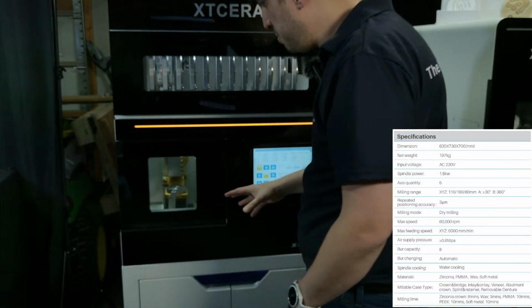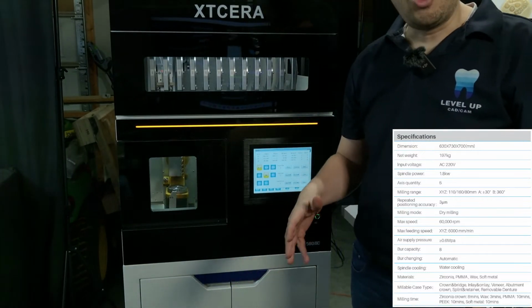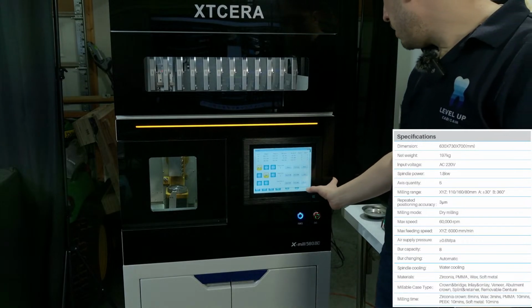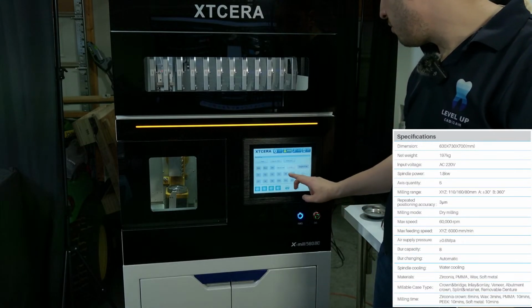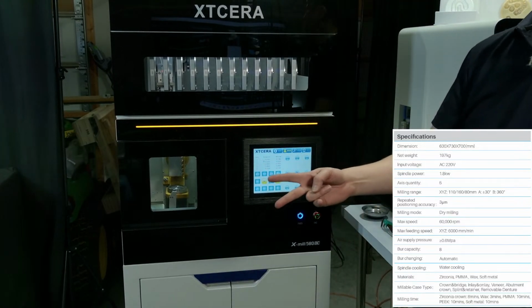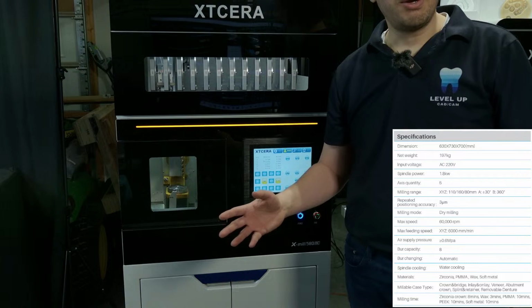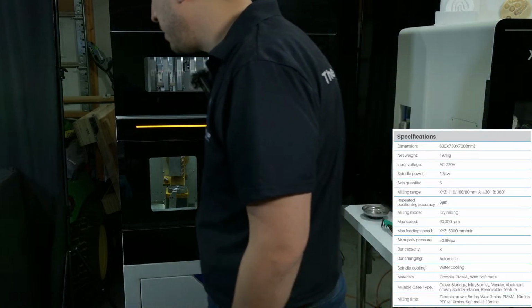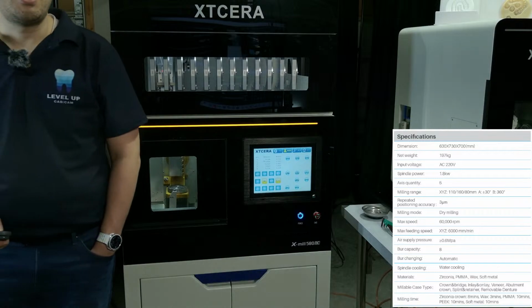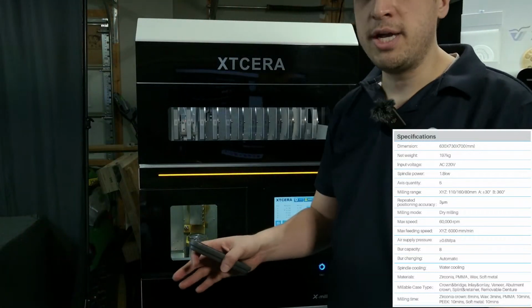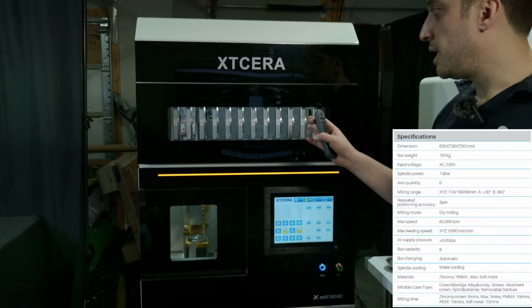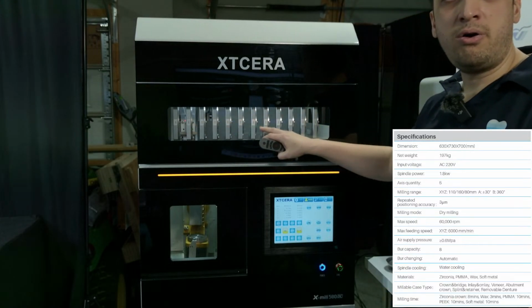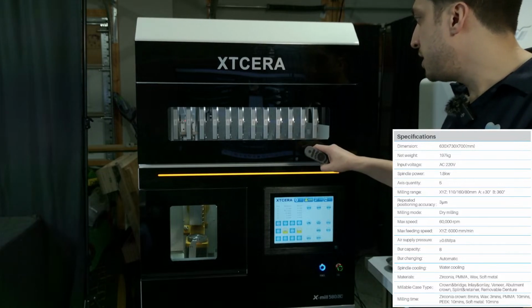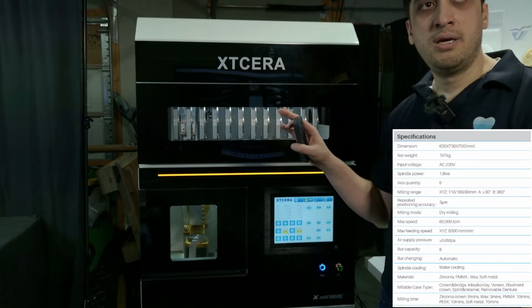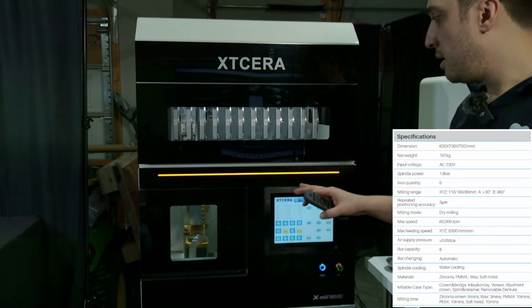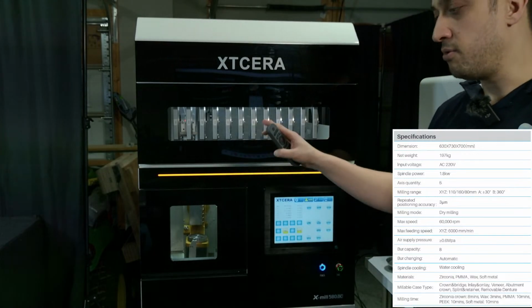Now, typically at this point, the machine is almost completely operational. The only other thing that I typically tend to do before I run these machines is, well, twofold. After it's been shipped, we always want to make sure that we calibrate the machine. So we're going to try to walk through a calibration, but before we do the calibration, another thing I like to do is I like to run through a cycle test of all the various disc adapters in the machine, just to make sure that we're not running into any robotic arm positional errors, also to make sure that the chucking mechanism and everything's working properly.